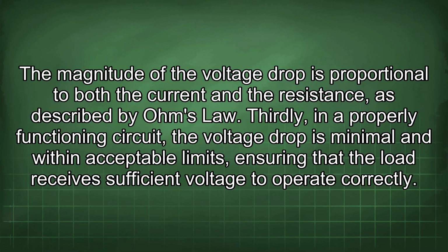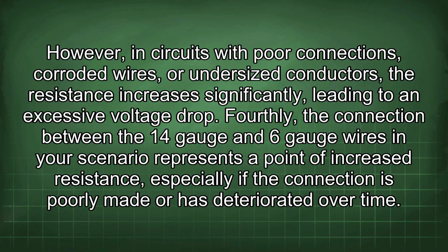Thirdly, in a properly functioning circuit, the voltage drop is minimal and within acceptable limits, ensuring that the load receives sufficient voltage to operate correctly. However, in circuits with poor connections, corroded wires, or undersized conductors, the resistance increases significantly, leading to an excessive voltage drop. Fourthly, the connection between the 14-gauge and 6-gauge wires in your scenario represents a point of increased resistance, especially if the connection is poorly made or has deteriorated over time.